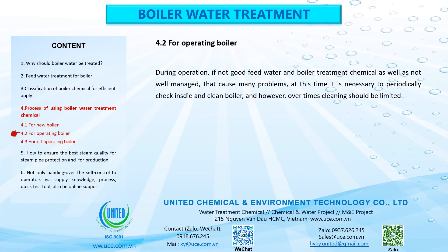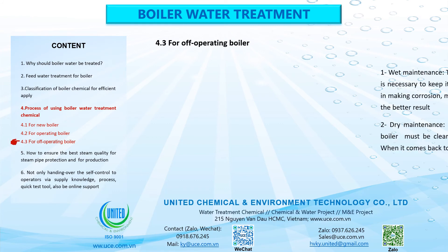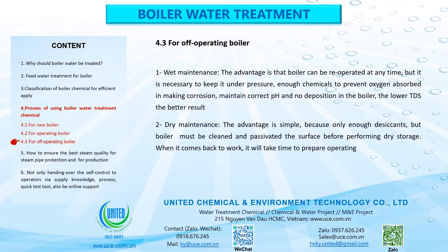4.2 For operating boiler. During operation, if feed water and boiler treatment chemicals are not good and management is not thorough, many problems can arise. It is necessary to periodically inspect and clean the boiler; however, over time, cleaning should be limited. 4.3 For off-operating boiler. 1. Wet maintenance: The advantage is that the boiler can be re-operated at any time, but it must be kept under pressure with sufficient chemicals to prevent oxygen absorption and corrosion, maintaining correct pH and no deposition. The lower the TDS, the better the result. 2. Dry maintenance: The advantage is simplicity — only enough desiccants needed — but the boiler must be cleaned and the surface passivated before performing dry storage. When returning to work, time will be needed to prepare for operation.